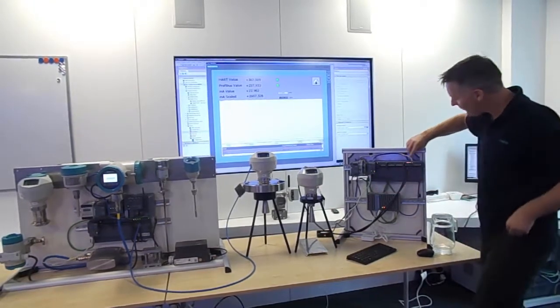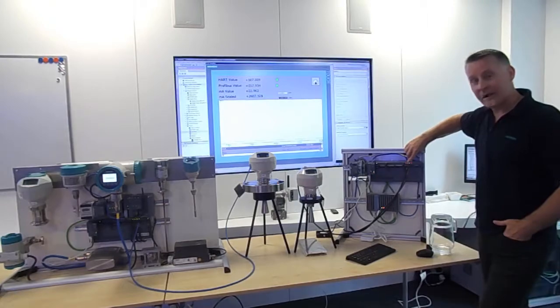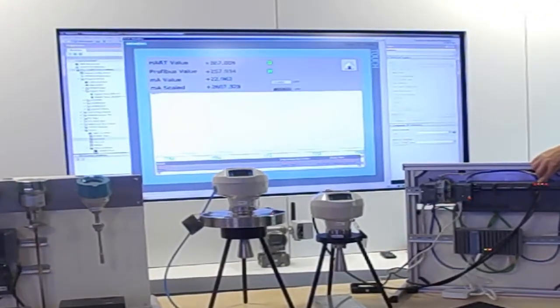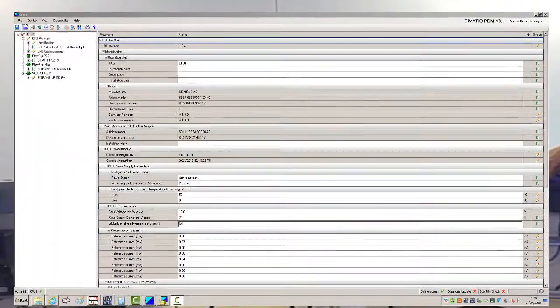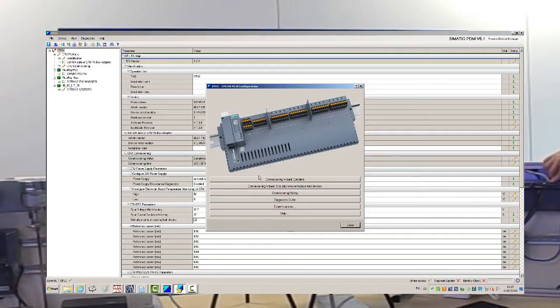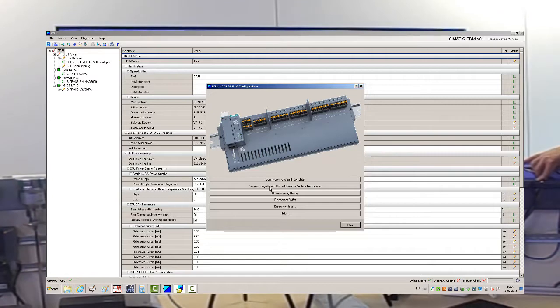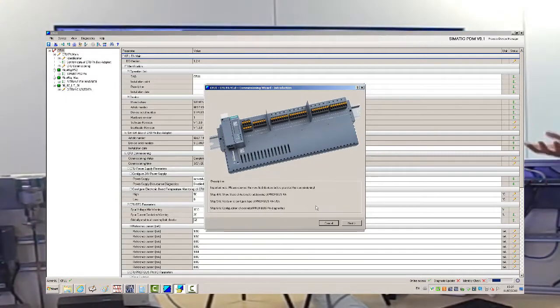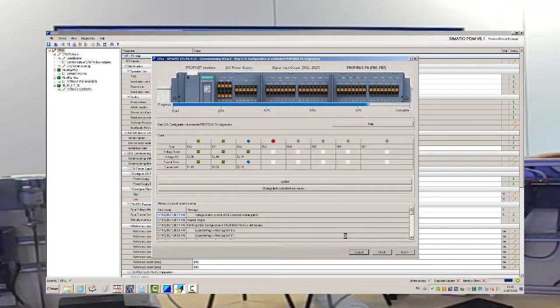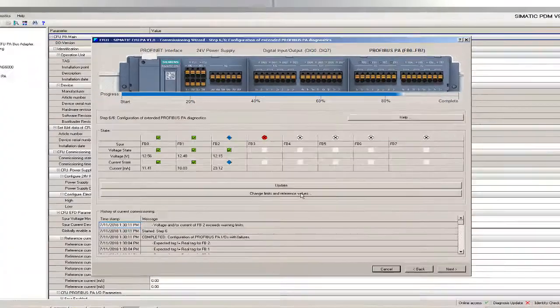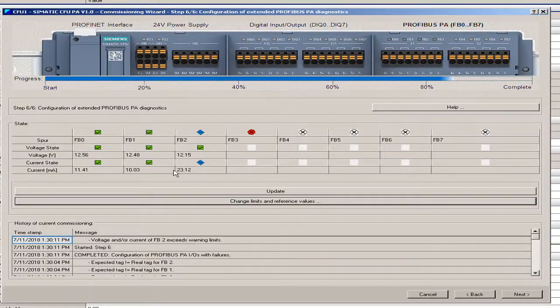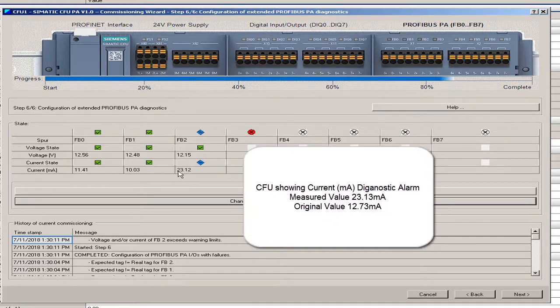Now we don't have that with the compact field unit because we don't have a network situation. What we can see the compact field unit has now gone to amber because it's monitoring the voltage. So we're still getting data. So we're not going to get a red flashing light like you can see here with these two that are open circuit. It's warning us that the conditions have changed. So that diagnostics is now coming back to my S7-1500. We're going to have a look at that in more detail with software tools, PDM and TIA portal over the next few screens.